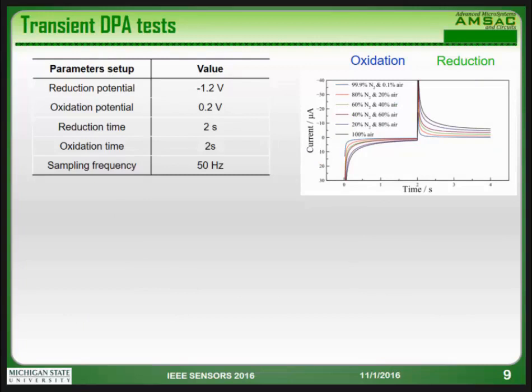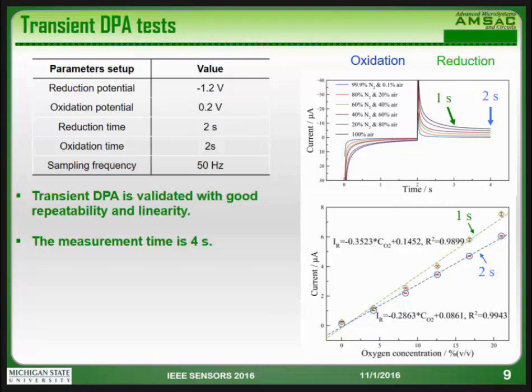So we performed the transient DPA test next. We tested six samples. Here shows the parameter setup. We optimized the different parameters here, and then we performed the test. From this test, we can see that the sensor responds differently to different concentrations of oxygen. Then we extracted the current at 1 second and 2 seconds, and we made the calibration, and it shows very good results. We performed 5 repeatable tests, and here shows the error bar. The repeatability is very good, and the linearity is also very good.